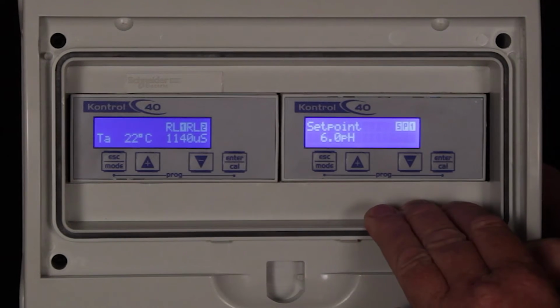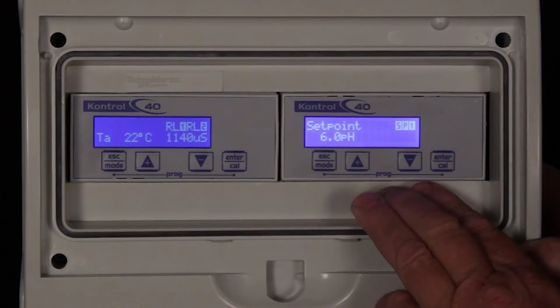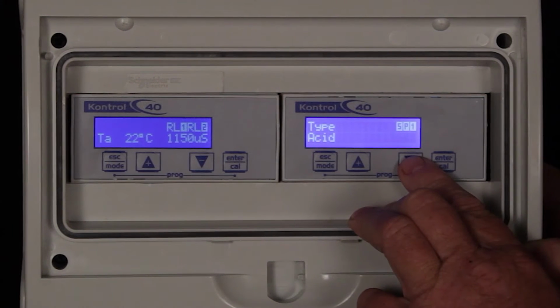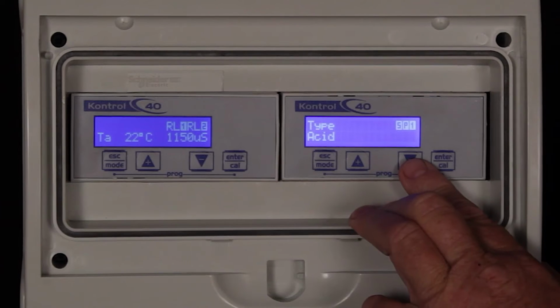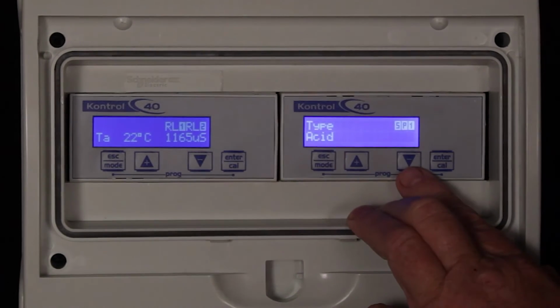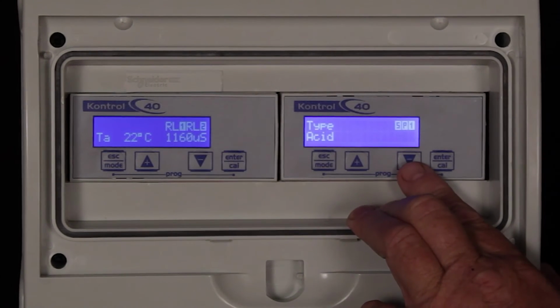To change the value, press enter and when it flashes, use the up or down arrows to increase or decrease the value. The next parameter is type. Your solution would be either alkaline or acidic. In this case, our water is alkaline, so I have to add some acid.